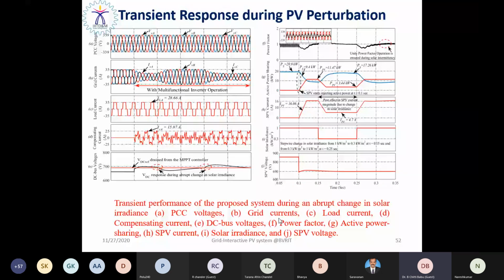And this is the transient response during PV perturbation. I told you that with the multifunctional inverter, as it acts as a shunt active power filter, it ensures power quality improvement. Without any controller, the supply current waveform is non-sinusoidal due to the introduction of a nonlinear load at the point of common coupling. But it becomes sinusoidal because this acts as a shunt active power filter, so that it injects the complementary component of the harmonic current present in the grid current, so that it shapes the grid current waveform sinusoidal. See the load current response, still it is a non-sinusoidal staircase waveform. And the compensating current is supplied by the inverter, so that it shapes the grid current waveform sinusoidal.